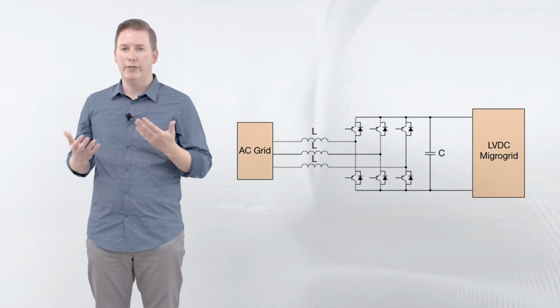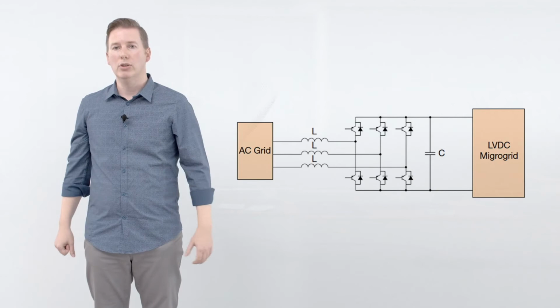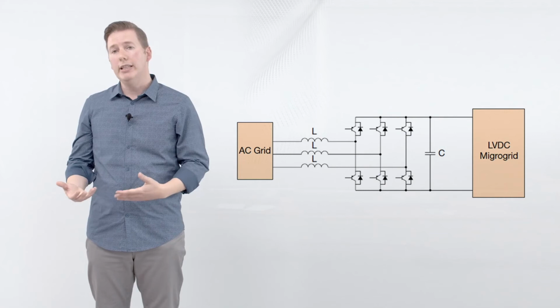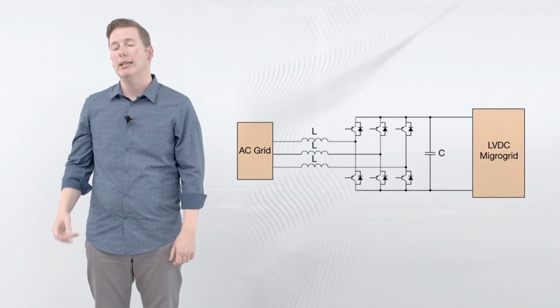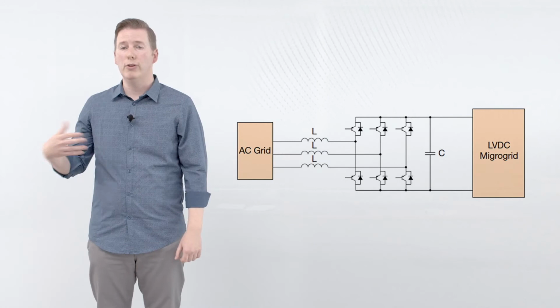Otherwise, if you'd like to use also the vehicle-to-grid function, usually a main AC-DC converter is made by the so-called IGBT-based converter. But also in this case, if you have a fault on DC side, the IGBTs are not able to limit nor interrupt the short circuit current, even if we send the blocking signal to the IGBT by the control system, since the current will flow through the so-called freewheeling diodes.